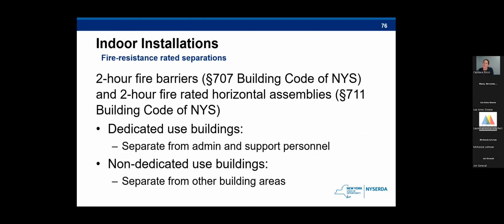And next, there's an additional fire resistance rated separation requirement for indoor installations. So 2-hour fire barriers are needed in a room or area for indoor installations. And horizontal assemblies refers to the ceilings as well as the walls. For dedicated use buildings, you need to have this 2-hour fire barrier separate from that admin and support personnel that's allowed to take up 10% of that building. And for non-dedicated use buildings, this 2-hour fire barrier needs to be separate from other building areas.